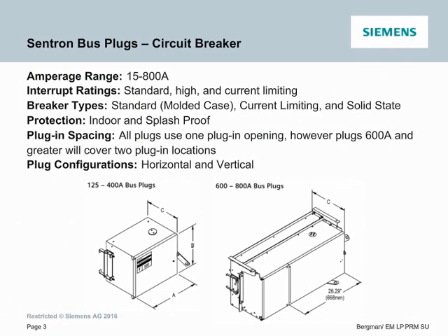And then in terms of plug-in spacing, it plugs up to 400 amps using one plug-in opening, 600 amps and greater use two plug-in openings, and it has both a horizontal and vertical configuration. As you probably already know, bus plugs are used to tap off power. We want to emphasize here that all bus plugs use the same plug-in base or connection method to the busway. This means that the plugs are interchangeable across different busway amperages. Additionally, this plug-in base is rated, as I mentioned, for 800 amps, and all bus plug amperages utilize this 800 amp design. These plugs are typically installed in industrial or high-rise applications.